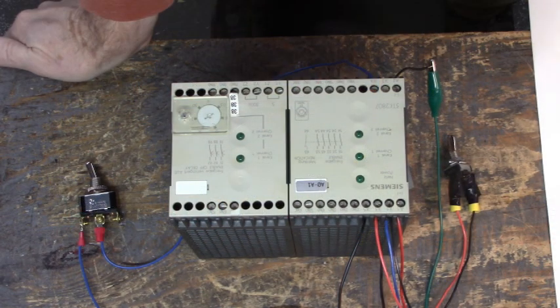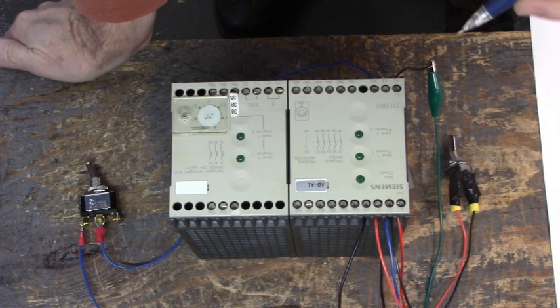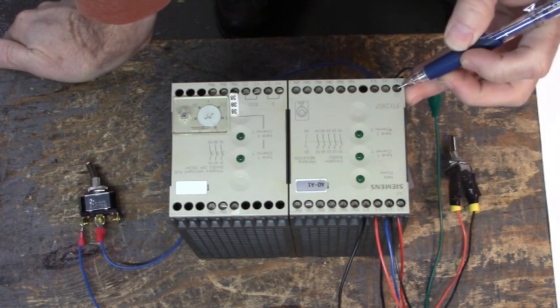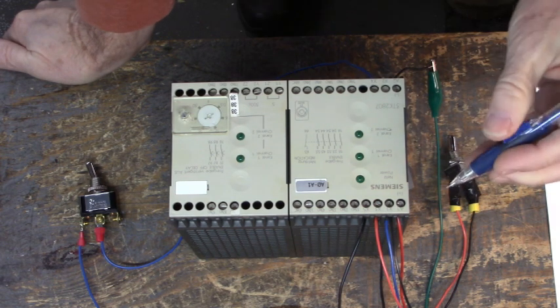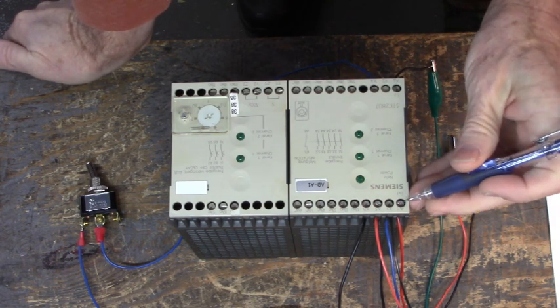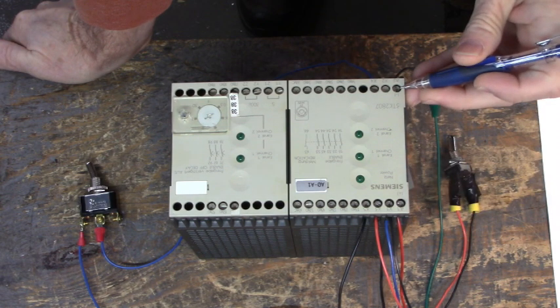Okay, we'll get close. Now, right here is the A1 terminal and the A2 terminal. On this unit right here, it's 24 volts to power it up. You apply positive 24 volts DC to A1, and it's ground to A2.